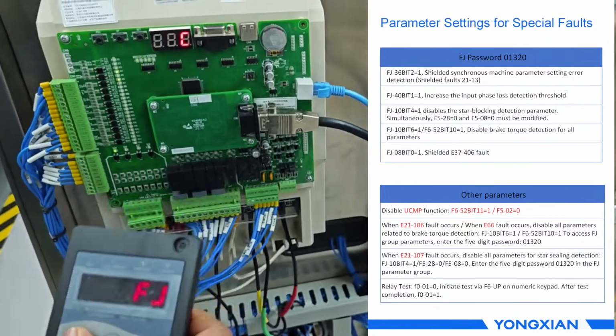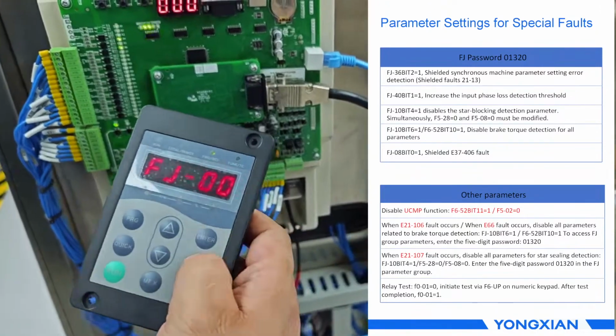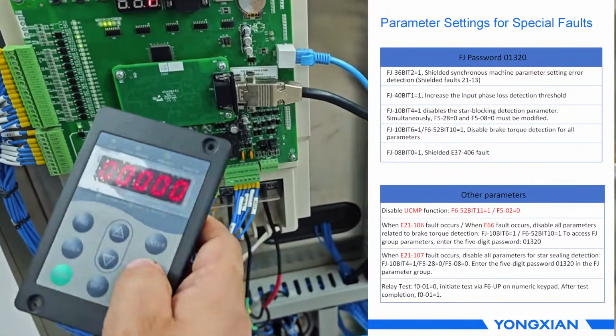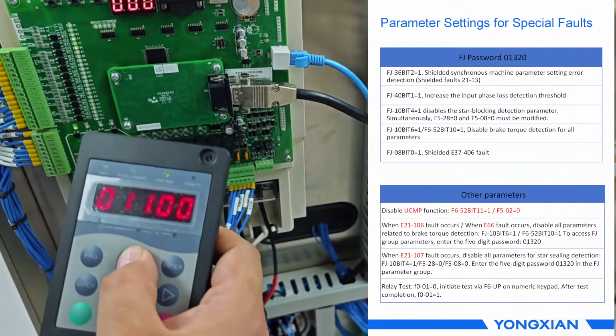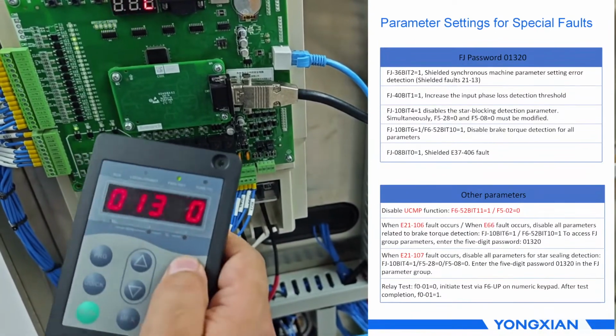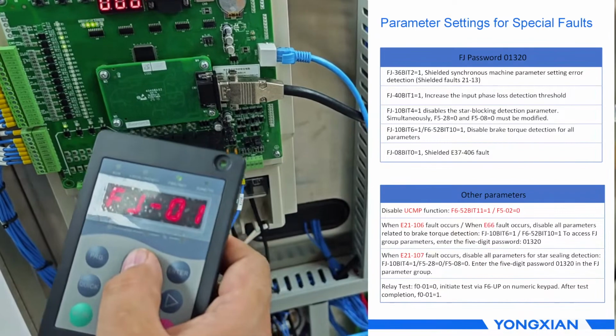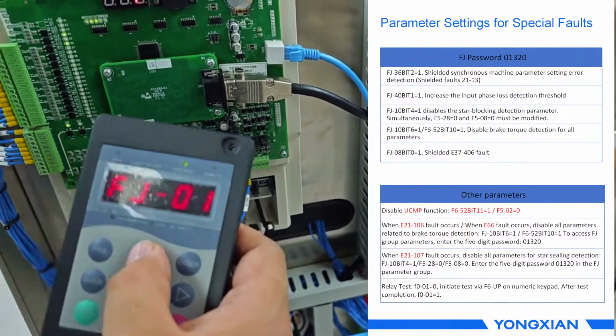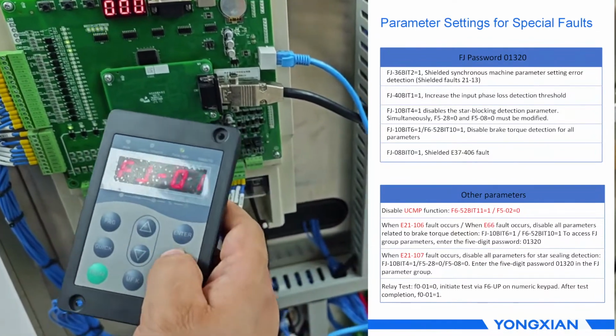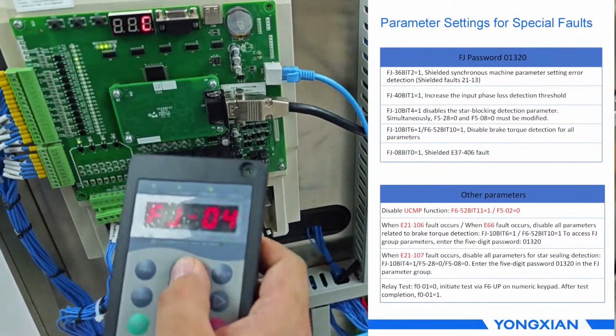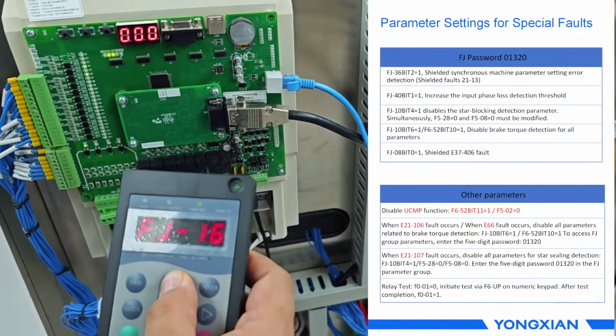然后还有一个 FJ-40。And the FJ 40 bit 1 equals 1. 是我们加大一个输入缺项判断的阈值。It's used to increase the input phase loss detection threshold.